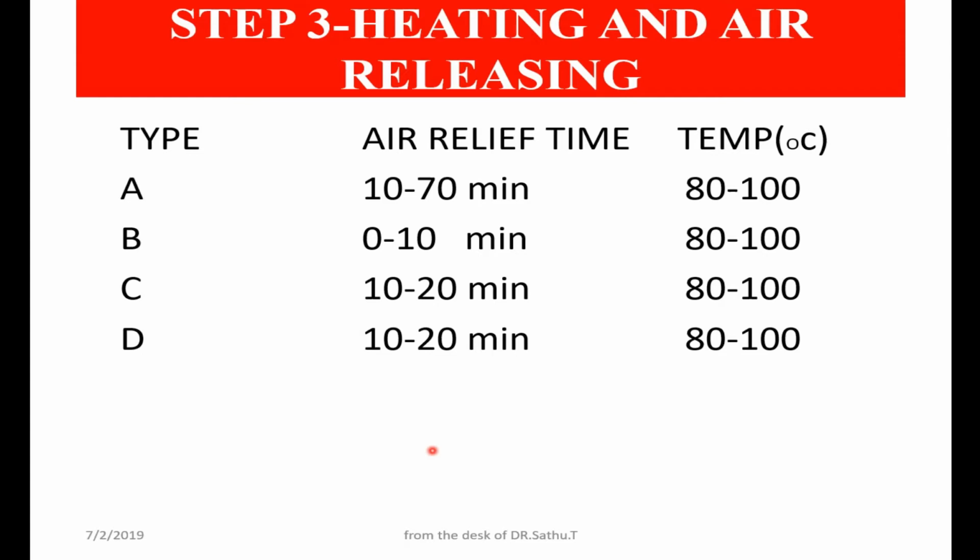Once you start heating, the water inside the raw material will get converted into steam, and after some time, when the temperature of the inner cooker or the material attains around 80 to 100 degrees centigrade, you can see the steam coming out. Once the steam starts coming out, you close the blow-off valve. It is similar to putting the weight on the cooker at home.